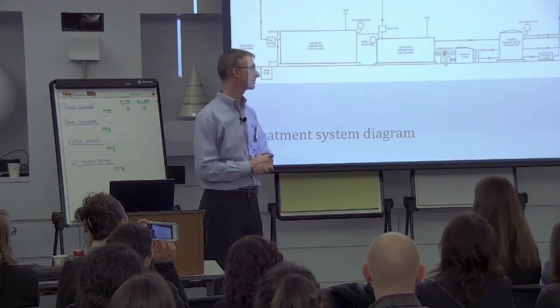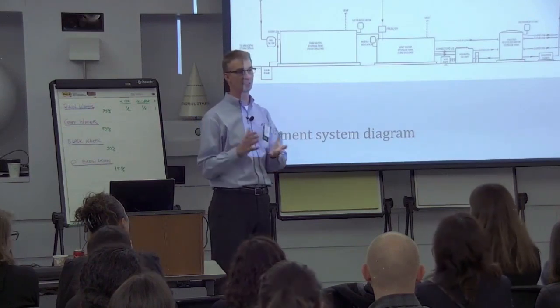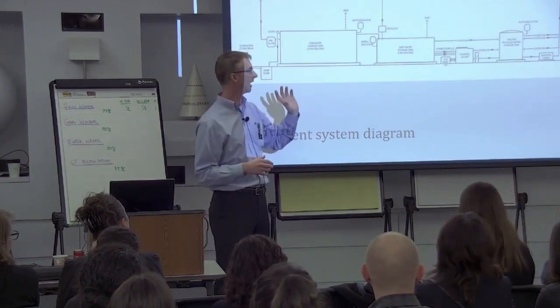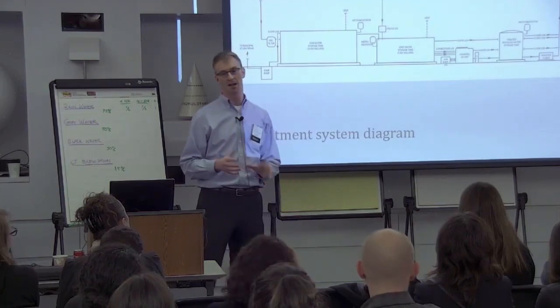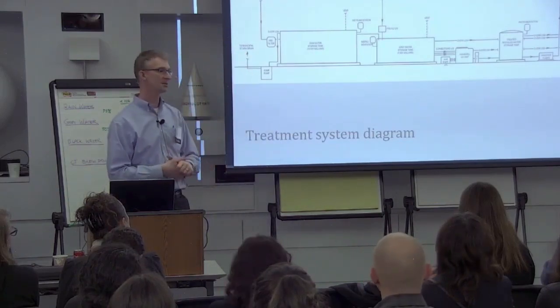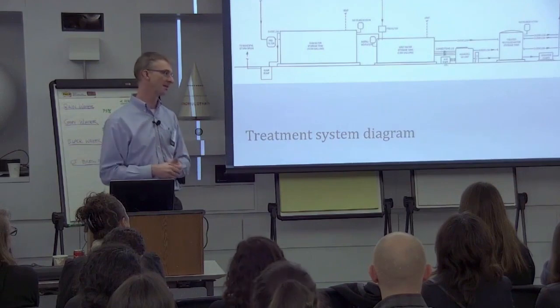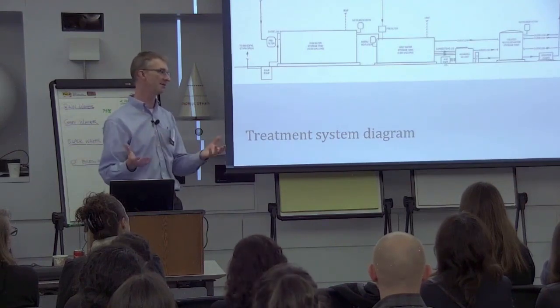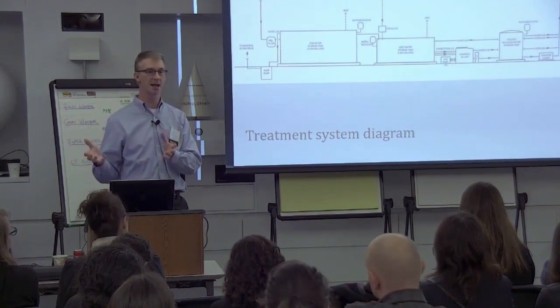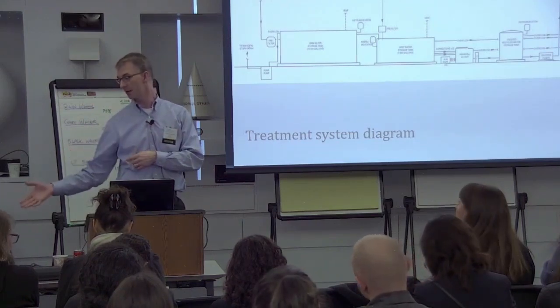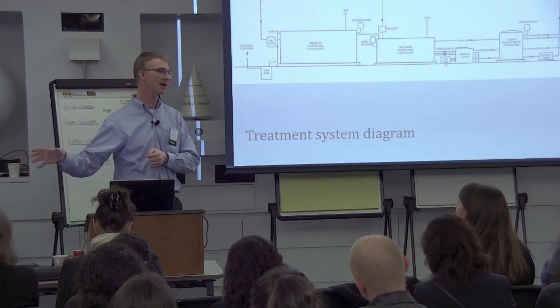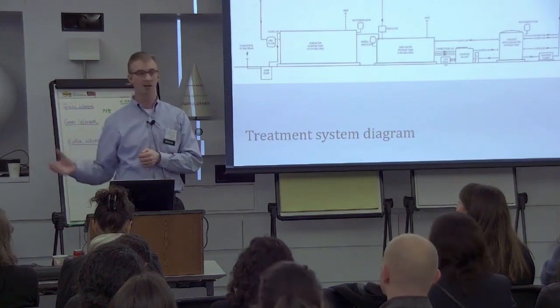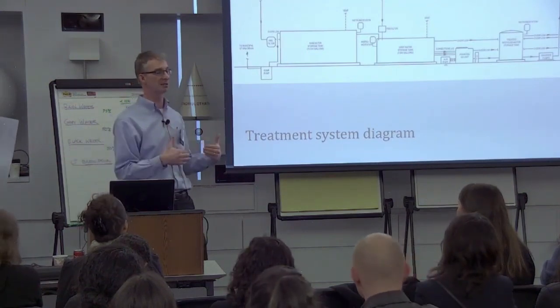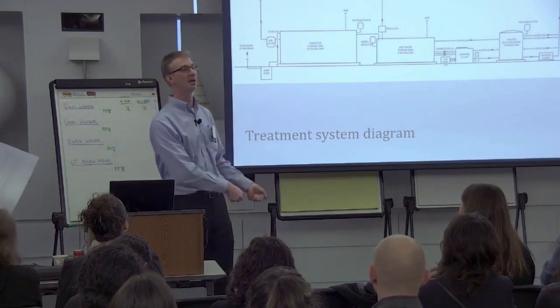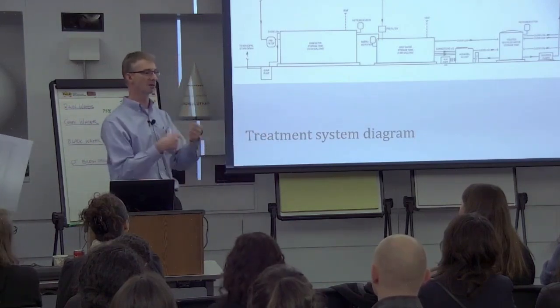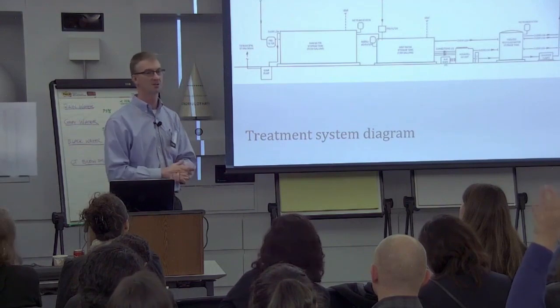It is 37 stories. So we have limited space for tanks and things. Our treated recycled water tank is currently at 7,500 gallons. We're going to try to make that as large as we can. Ideally, we would have 25,000 gallons, which would meet all of our one day, or that would be our one month, actually. But we definitely want to have the daily demand, and we'd love to get as much as we can, because then we can shut down for maintenance of the treatment system without switching over to the potable water backup.